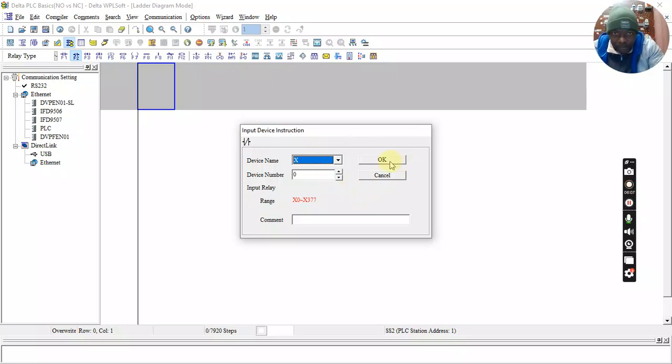Now, our x0, can you see, this is the difference with physical components, with hardwiring. With hardwiring, if a specific contact is normally closed, there is no way you can then decide it's going to be normally open, and vice versa. With the software, I can decide if a specific contact is open or closed. So this same x0, I can decide I don't want it normally open, I want it normally closed. Previously, we've been dealing with it as normally open. Now we're saying we want it normally closed.